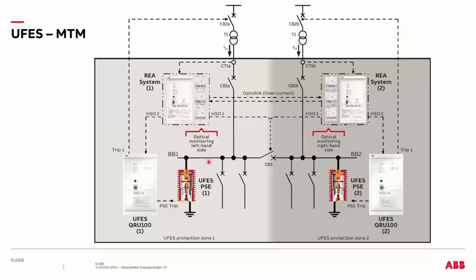So if there is an arcing fault on this bus bar 1, the REA is going to send a signal to the REA system on bus bar 2, so that it's not going to trip your main breaker on B side, whereas the system 1 is going to trip the main incoming breaker as well as your tie breaker. So it's going to isolate this particular section when you have an arcing fault somewhere in this particular equipment on the bus bar 1 side.